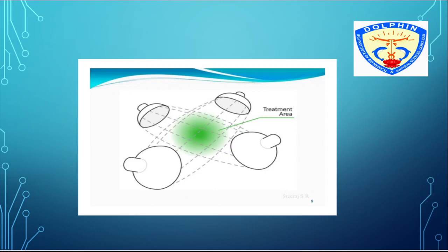2 red and 2 black electrodes are used with different frequencies, and all are medium frequency currents. As you know, it ranges from 1000 to 10,000 hertz. So both are medium frequency currents, and when they cross at the point where we are using the current, they form a beat frequency, a low frequency current of 50 hertz, which is very appropriate for the healing procedure, for therapeutic purposes. So this is the diagram, you can see clearly.